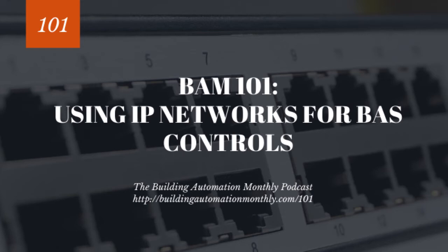It's a good question, and you're seeing it already. A lot of IP-enabled controllers are hosting the whole solution on their own. The difference in controller architecture is where you're placing these. Think of a strip mall with a small store in it. Do they really need a fully enabled commercial control system? Maybe, but if they're only a single tenant not connected to a major control system, you could run your single rooftop unit with a graphic-enabled controller and still have access and maintain energy savings, but only in your local area.